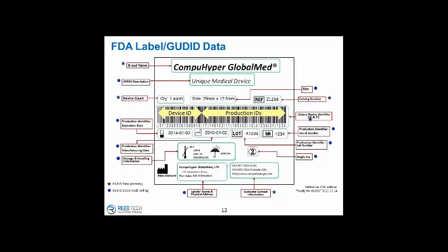Yeah, that's a really good question. So again, this is an FDA illustrative label. Not all these fields would be required. Obviously, a keep dry, and in particular, Joe, you had mentioned the question that came up about single-use down here. Some of these icons are not required, and they're only applicable if it's appropriate for your particular product.